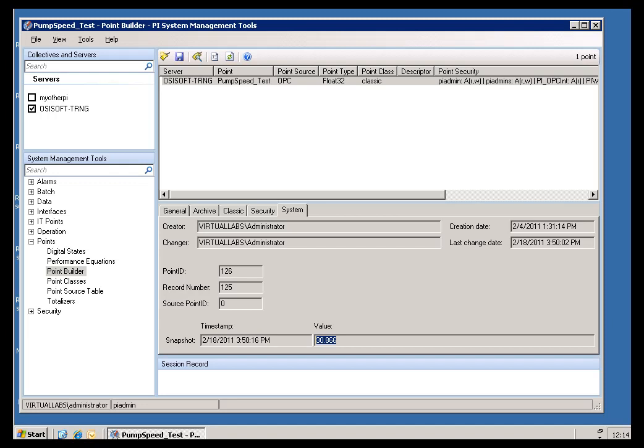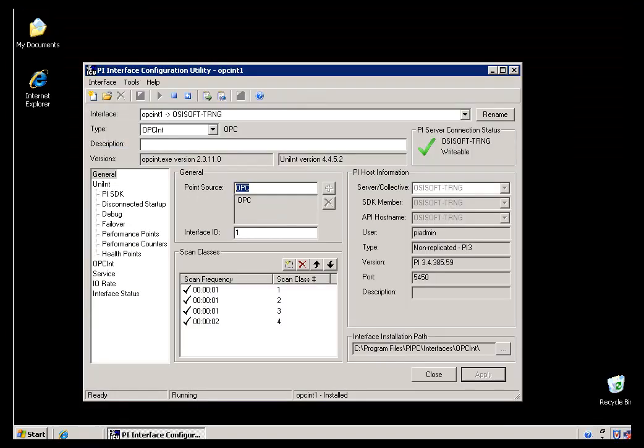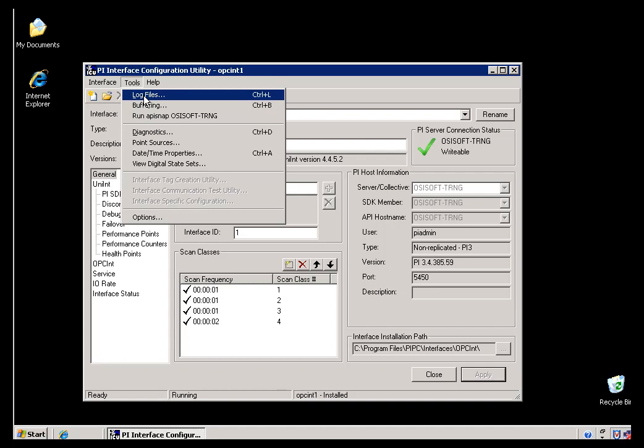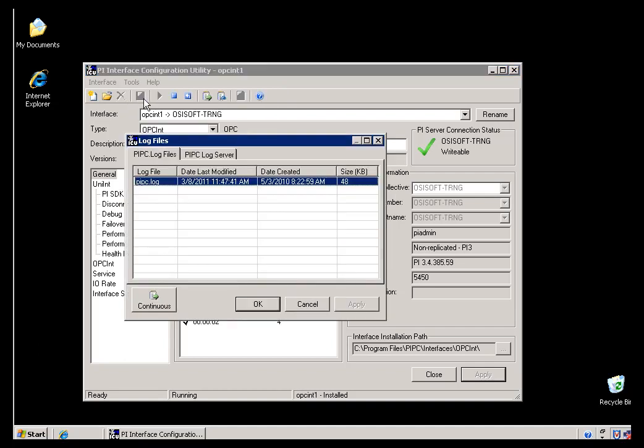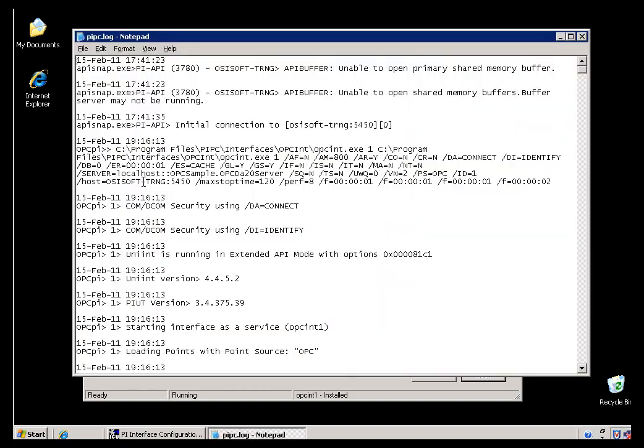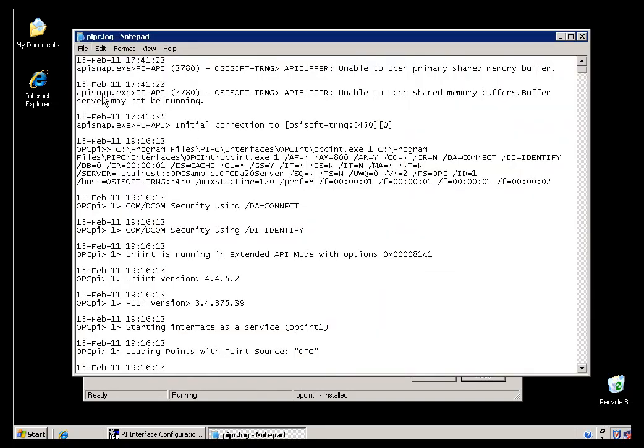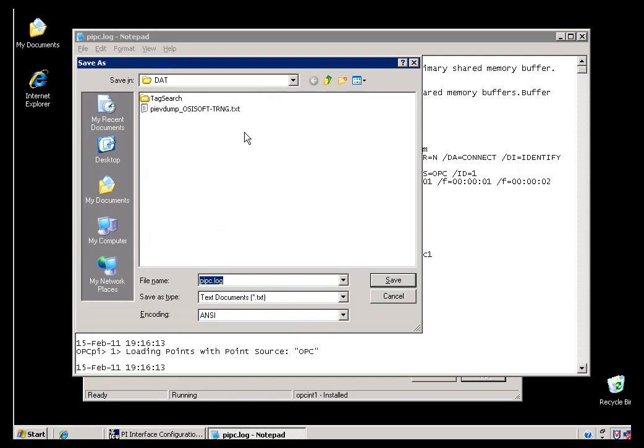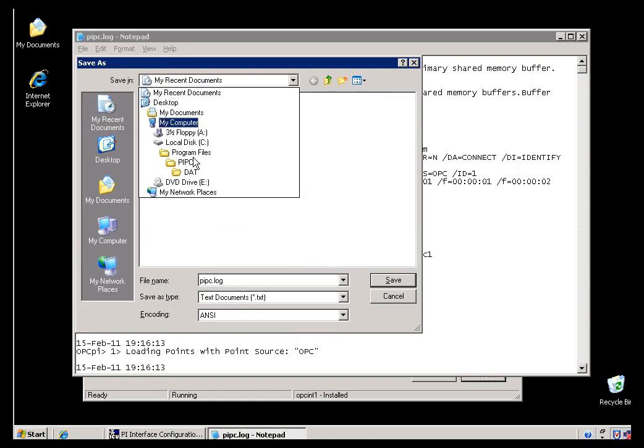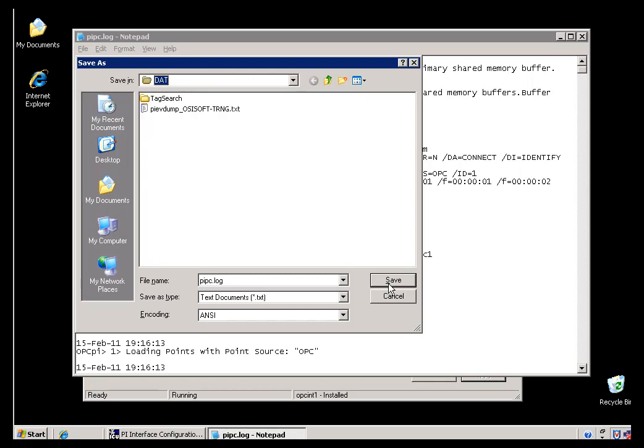I'll go back to the Interface Node, and I'll open up the Log File. I can do that a couple of ways. I can go into the pipc slash dat directory, and I can look for the file called pipc.log, or I can just go into ICU, Interface Configuration Utility, and this is where you can find that log. You can see this is where we normally store that log, pipc slash dat.